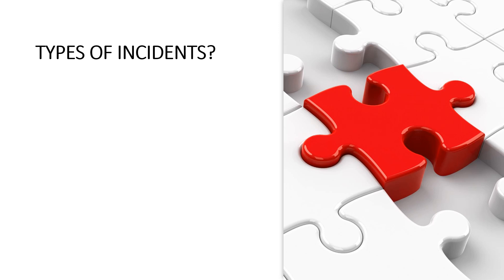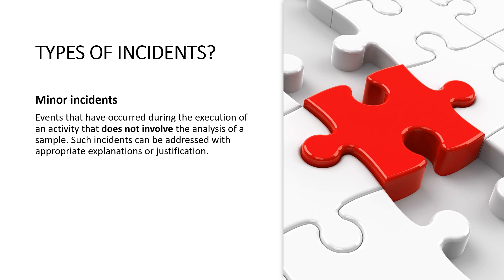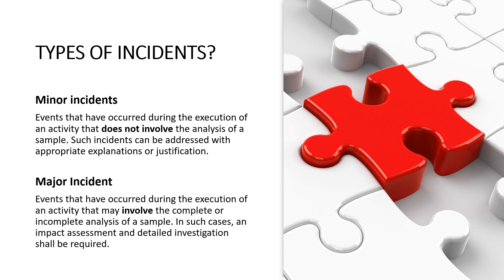There are two types of incidents: minor and major. Minor incidents are those events that occur during the execution of an activity that does not involve the analysis of a sample. Such incidents can be addressed with appropriate explanation and justification — meaning they have no impact on product quality. For example, when product analysis is performed on an HPLC instrument and the incident is observed before the injection or analysis of a sample, it shall be considered a minor incident.